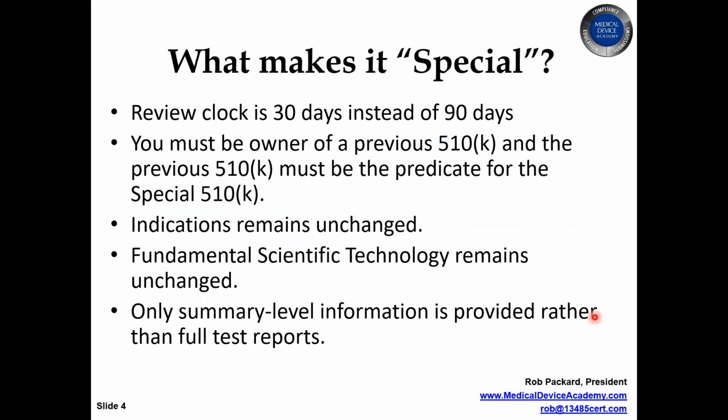So what makes a special 510K? What makes it special? Why do they use that term? First of all, special 510Ks are shorter. Instead of a 90-day review, which is what the FDA's goal is for traditional 510Ks, it's only 30 days. And in order to get their entire review done and make a decision on whether your device is substantially equivalent in 30 days, there are some requirements.